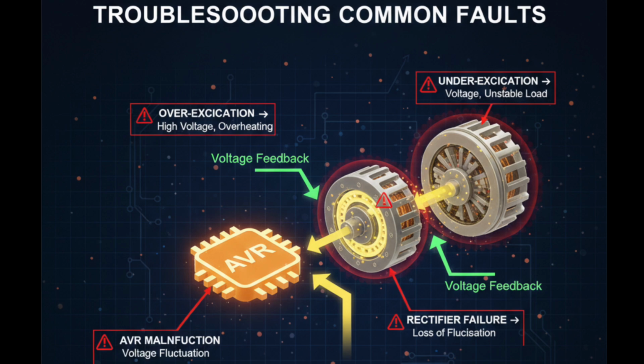Troubleshooting involves stepwise checks. Measure output AC, check rotor DC voltage, inspect rectifier diodes, and verify AVR response. Following the flow illustrated in the graphics makes fault detection faster and more accurate. For exams, focus on fault causes, indicators, and corrective actions, as these are frequently asked in oral and practical assessments.